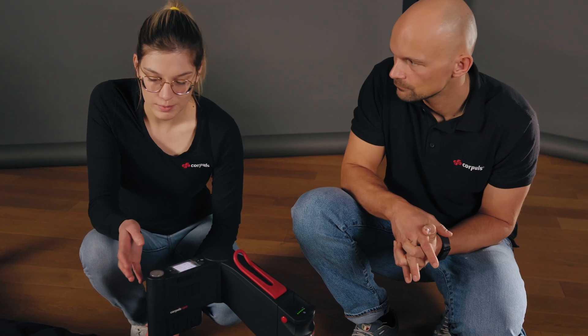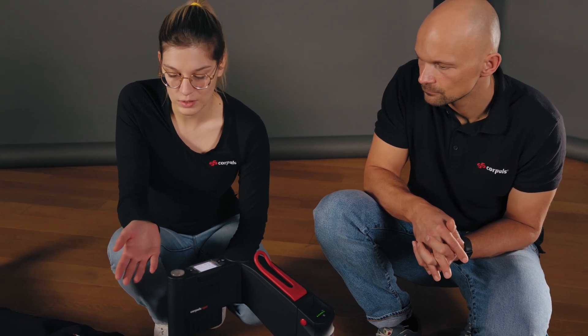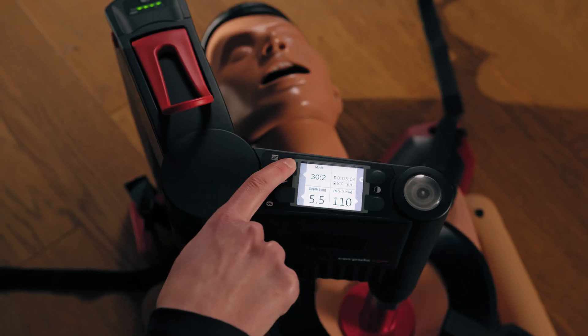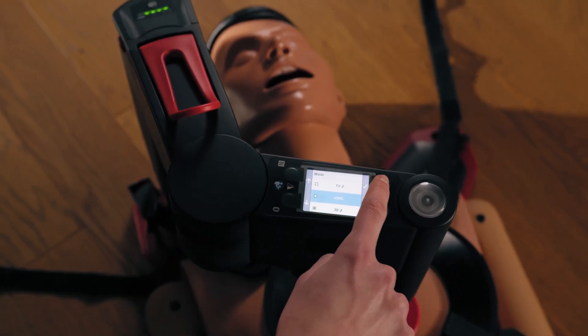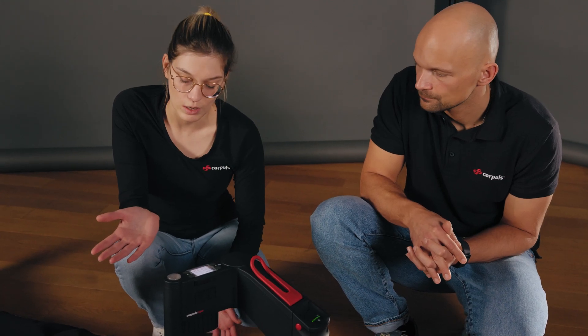What usually happens is that you start a resuscitation under standard conditions in 30:2 mode. During the course of the resuscitation the airway is secured, and you want to change the mode to continuous. To do so, press the corresponding soft key next to the mode, select from the list, confirm this, and either go back using the back button or, if you don't press anything, it automatically jumps back after three seconds.